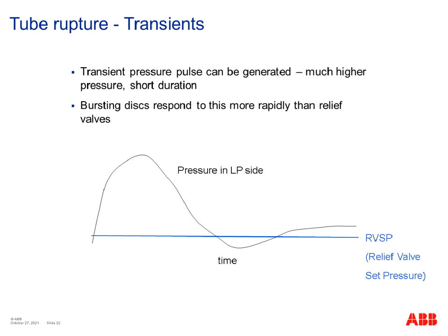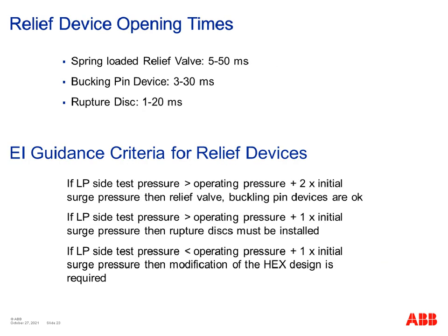So a number of factors affect the peak pressure generated in this event. These factors include things like the heat exchanger configuration, the pressures, the tube diameters, the shell diameter, what relief device you've got, the baffle arrangement, and so on. So lots of things related to the internal geometry of the exchanger have an impact on what the peak pressure might be in this event. So the answer to the question about why heat exchangers often have bursting discs instead of relief valves is that bursting discs open more quickly than relief valves, and they therefore can reduce the peak pressures in time to prevent the overpressure in the exchanger and prevent rupture.